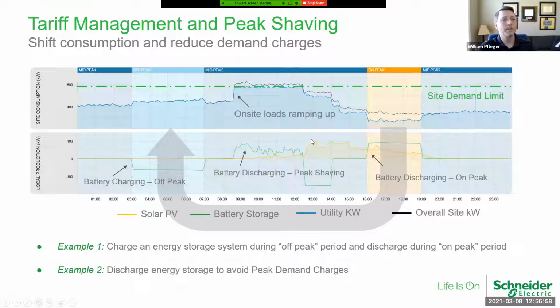After the solar came back up and the HVAC system had gotten the building comfortable, the load starts to drop off. You might be puzzled because this line represents the battery charging not at the cheapest time period, but the platform had already looked ahead and knew we were about to enter a more expensive time period. Having that additional capacity in the battery available to discharge at an expensive time was more valuable than the savings of purchasing that energy later when it was least expensive. So it charged at not the cheapest time to get more savings in cost avoidance during the most expensive time. That's the real beauty of this platform.